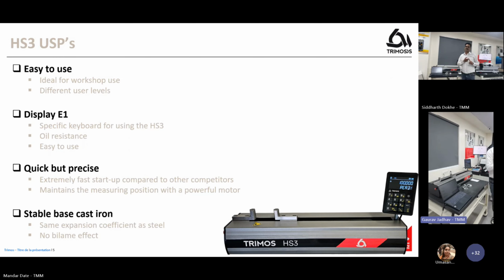You maintain one master machine. You can calibrate it once or twice a year depending on frequency of use. If you're using it on the shop floor, you can calibrate within a year and just maintain one master. Within the range, you can set any size required to set bore gauges, internal micrometers, or external micrometers. So 2-point measuring instruments can be set at any level, even down to a micron size.